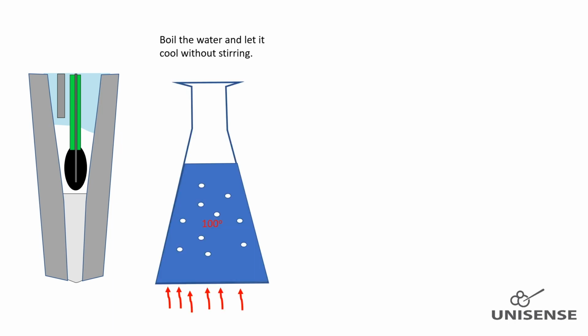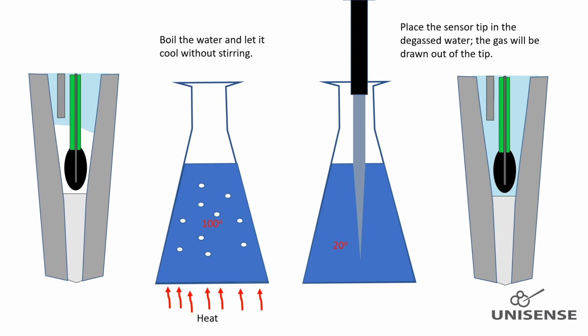Fill water into a glass bottle and boil the water. This drags gases out of the water. Let the water cool to room temperature or below without shaking the bottle or mixing the water. Place the sensor tip into the water for some hours. The gas phase will be removed by this procedure.